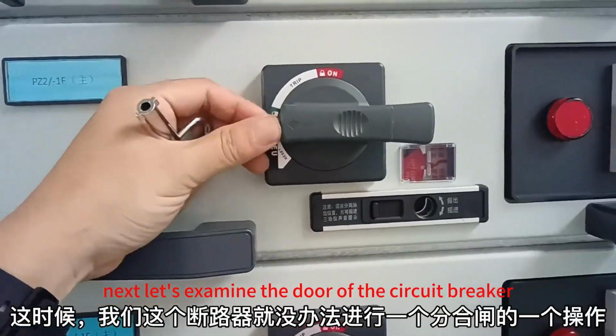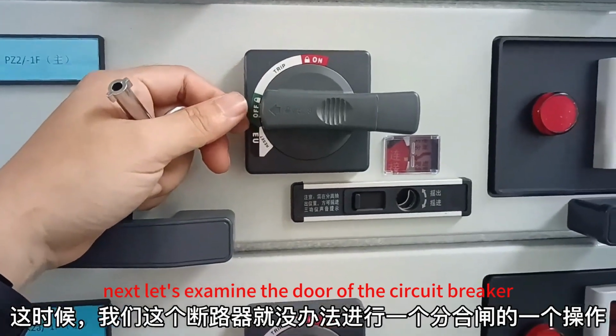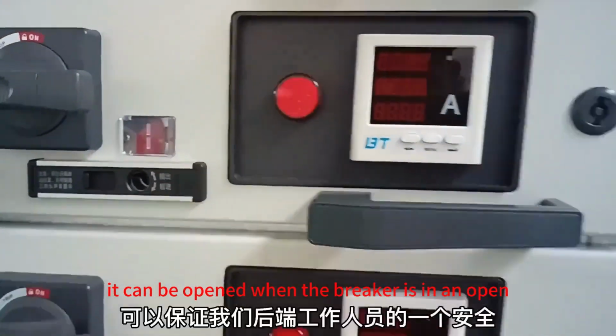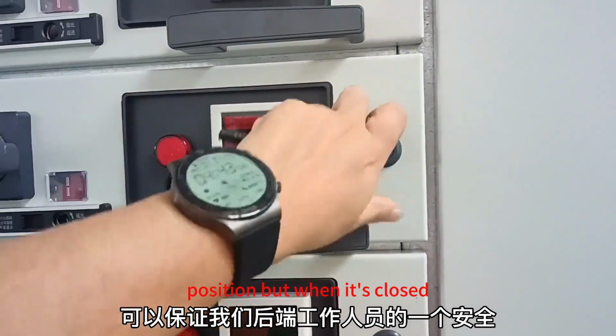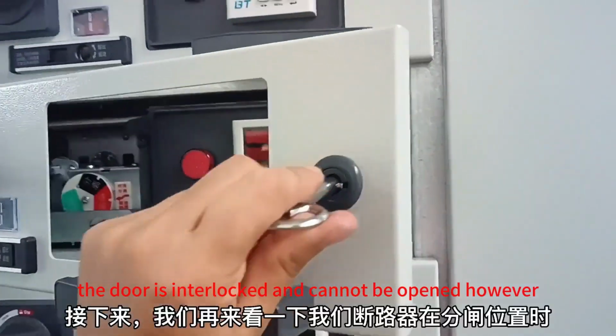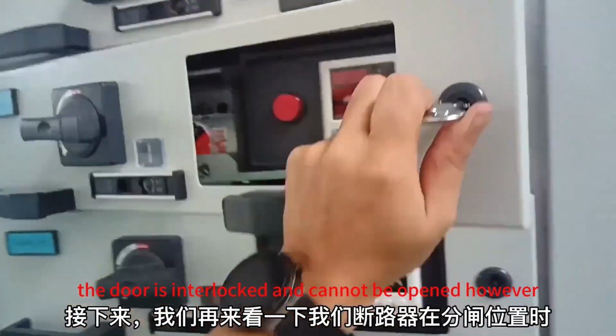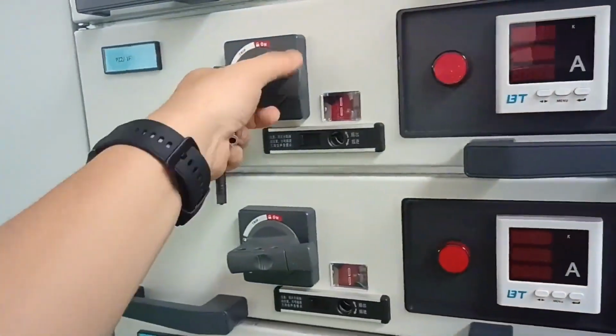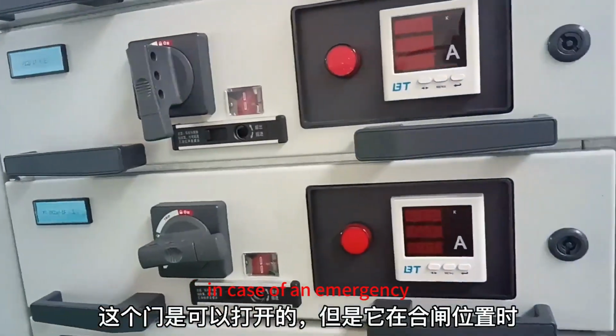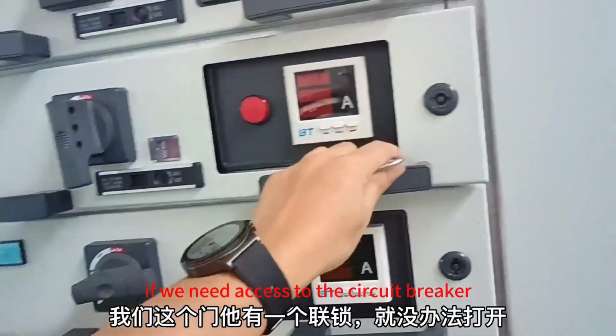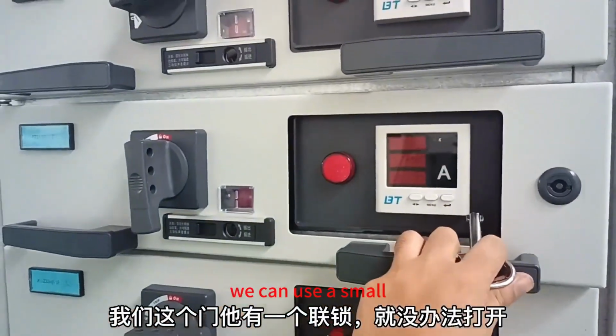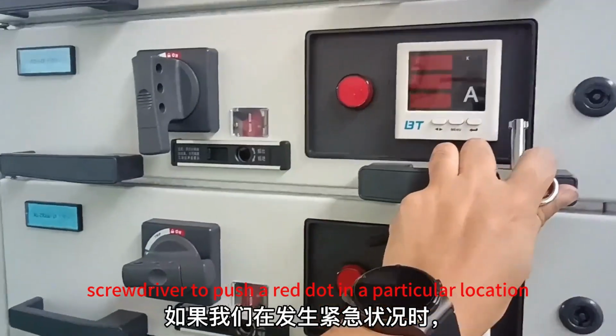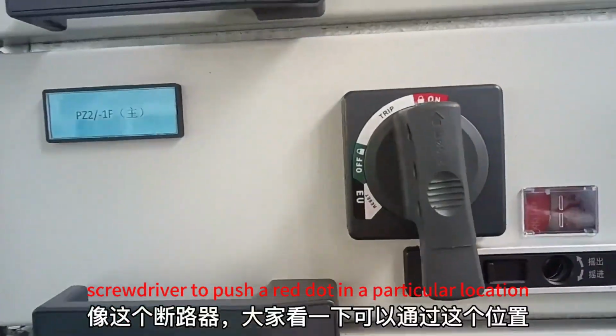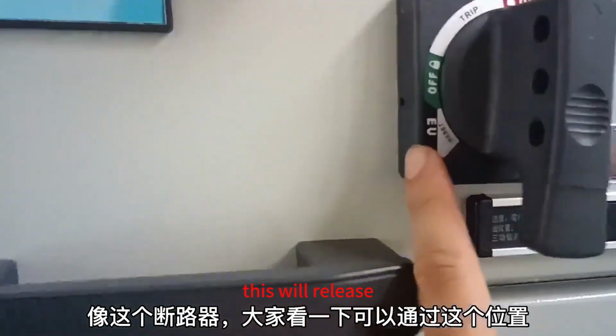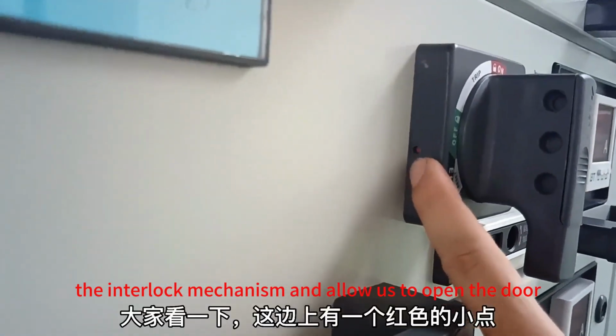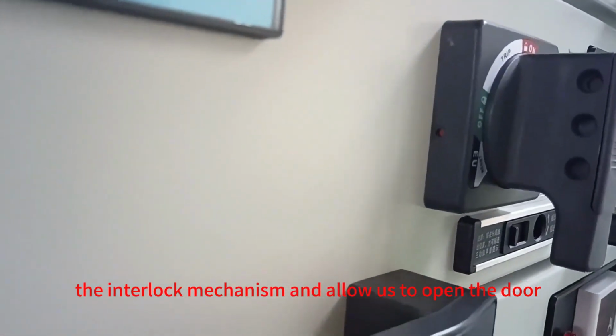Next, let's examine the door of the circuit breaker. It can be opened when the breaker is in an open position, but when it's closed, the door is interlocked and cannot be opened. However, in case of an emergency, if we need access to the circuit breaker, we can use a small screwdriver to push a red dot in a particular location. This will release the interlock mechanism and allow us to open the door.